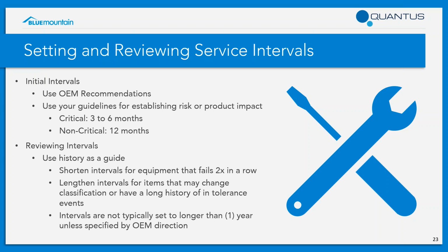On average, we typically see services performed every 6 to 12 months, with those super critical devices performed every 3 months. We've also gotten a lot of questions over the years about going beyond 12 months and when that is acceptable. And it really boils down to a few items. Your risk assessment, of course, for potential impact areas, and then the inherent stability or historic stability of the instrument. So if you're using something like a physical go, no-go gauge, that may only require testing every 3 to 5 years because it's a physical device. It doesn't have electronic drift. And if it's not damaged, in most cases, it's going to have a good amount of stability.